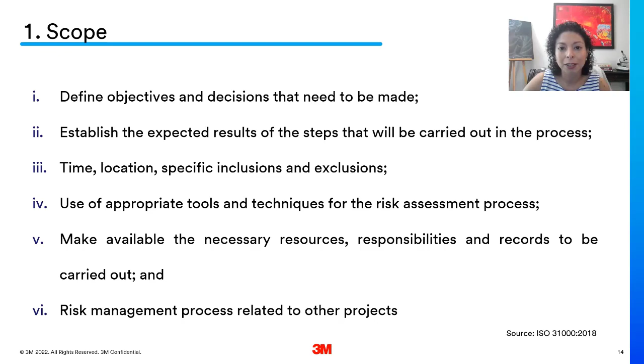So here's an example of a project that took place. They were evaluating cleaning lumened items within the ultrasonic washers. And so step number one, their objective was to mitigate the risk of soil in lumened instruments after cleaning in the ultrasonic washer. That was their goal. Their hope was to result in ATP cleaning tests with a value less than 30 RLUs. And so that was what they hoped to gain at the end of the process. The time, location, and specific inclusions: only for 30 days, instruments with lumened items smaller than 5 millimeters were going to be monitored.